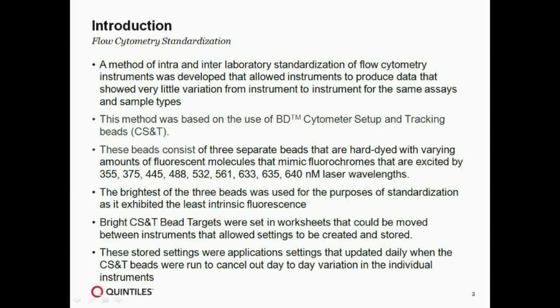This allowed us to set bright bead targets that could be used in a worksheet sent across various sites, providing standardization information based on that bead easily across multiple sites simply by emailing a worksheet. These were then used to create application settings — a feature of the software — that could be stored and updated daily. If you don't have application settings, you can still standardize daily by setting to the targets and then compensating the instruments. It's possible to standardize any instrument by this method.